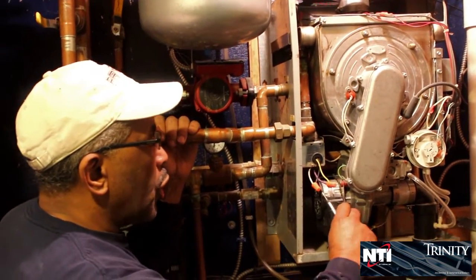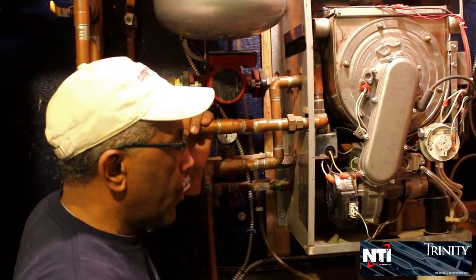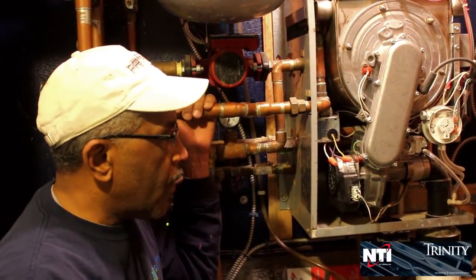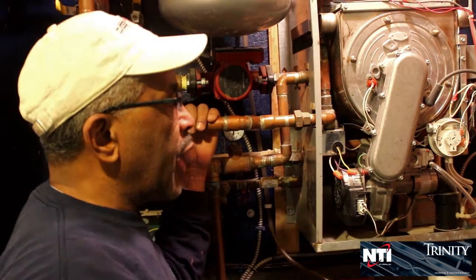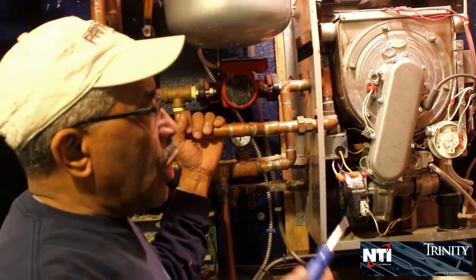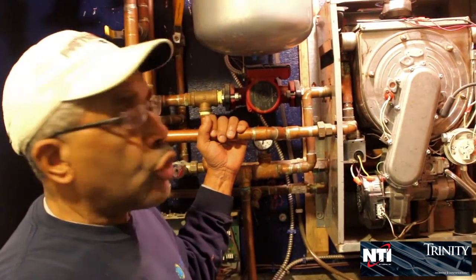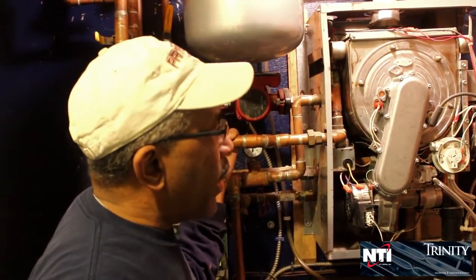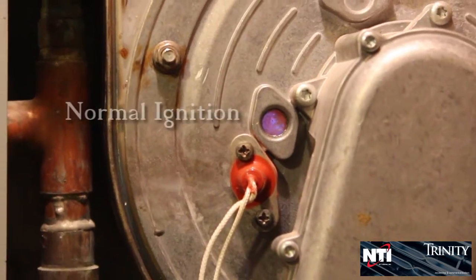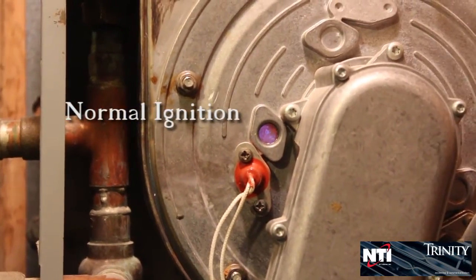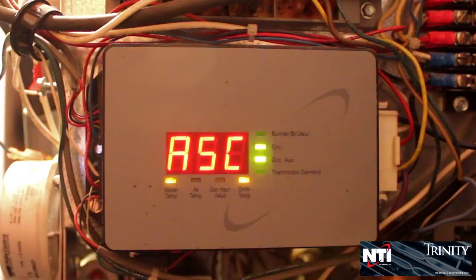You're going to reinsert the plug into the inducer motor, and you're going to wait about 5 seconds. The ASC code should go away on the controller and the boiler should light normally. So let's take a look and see how this works.